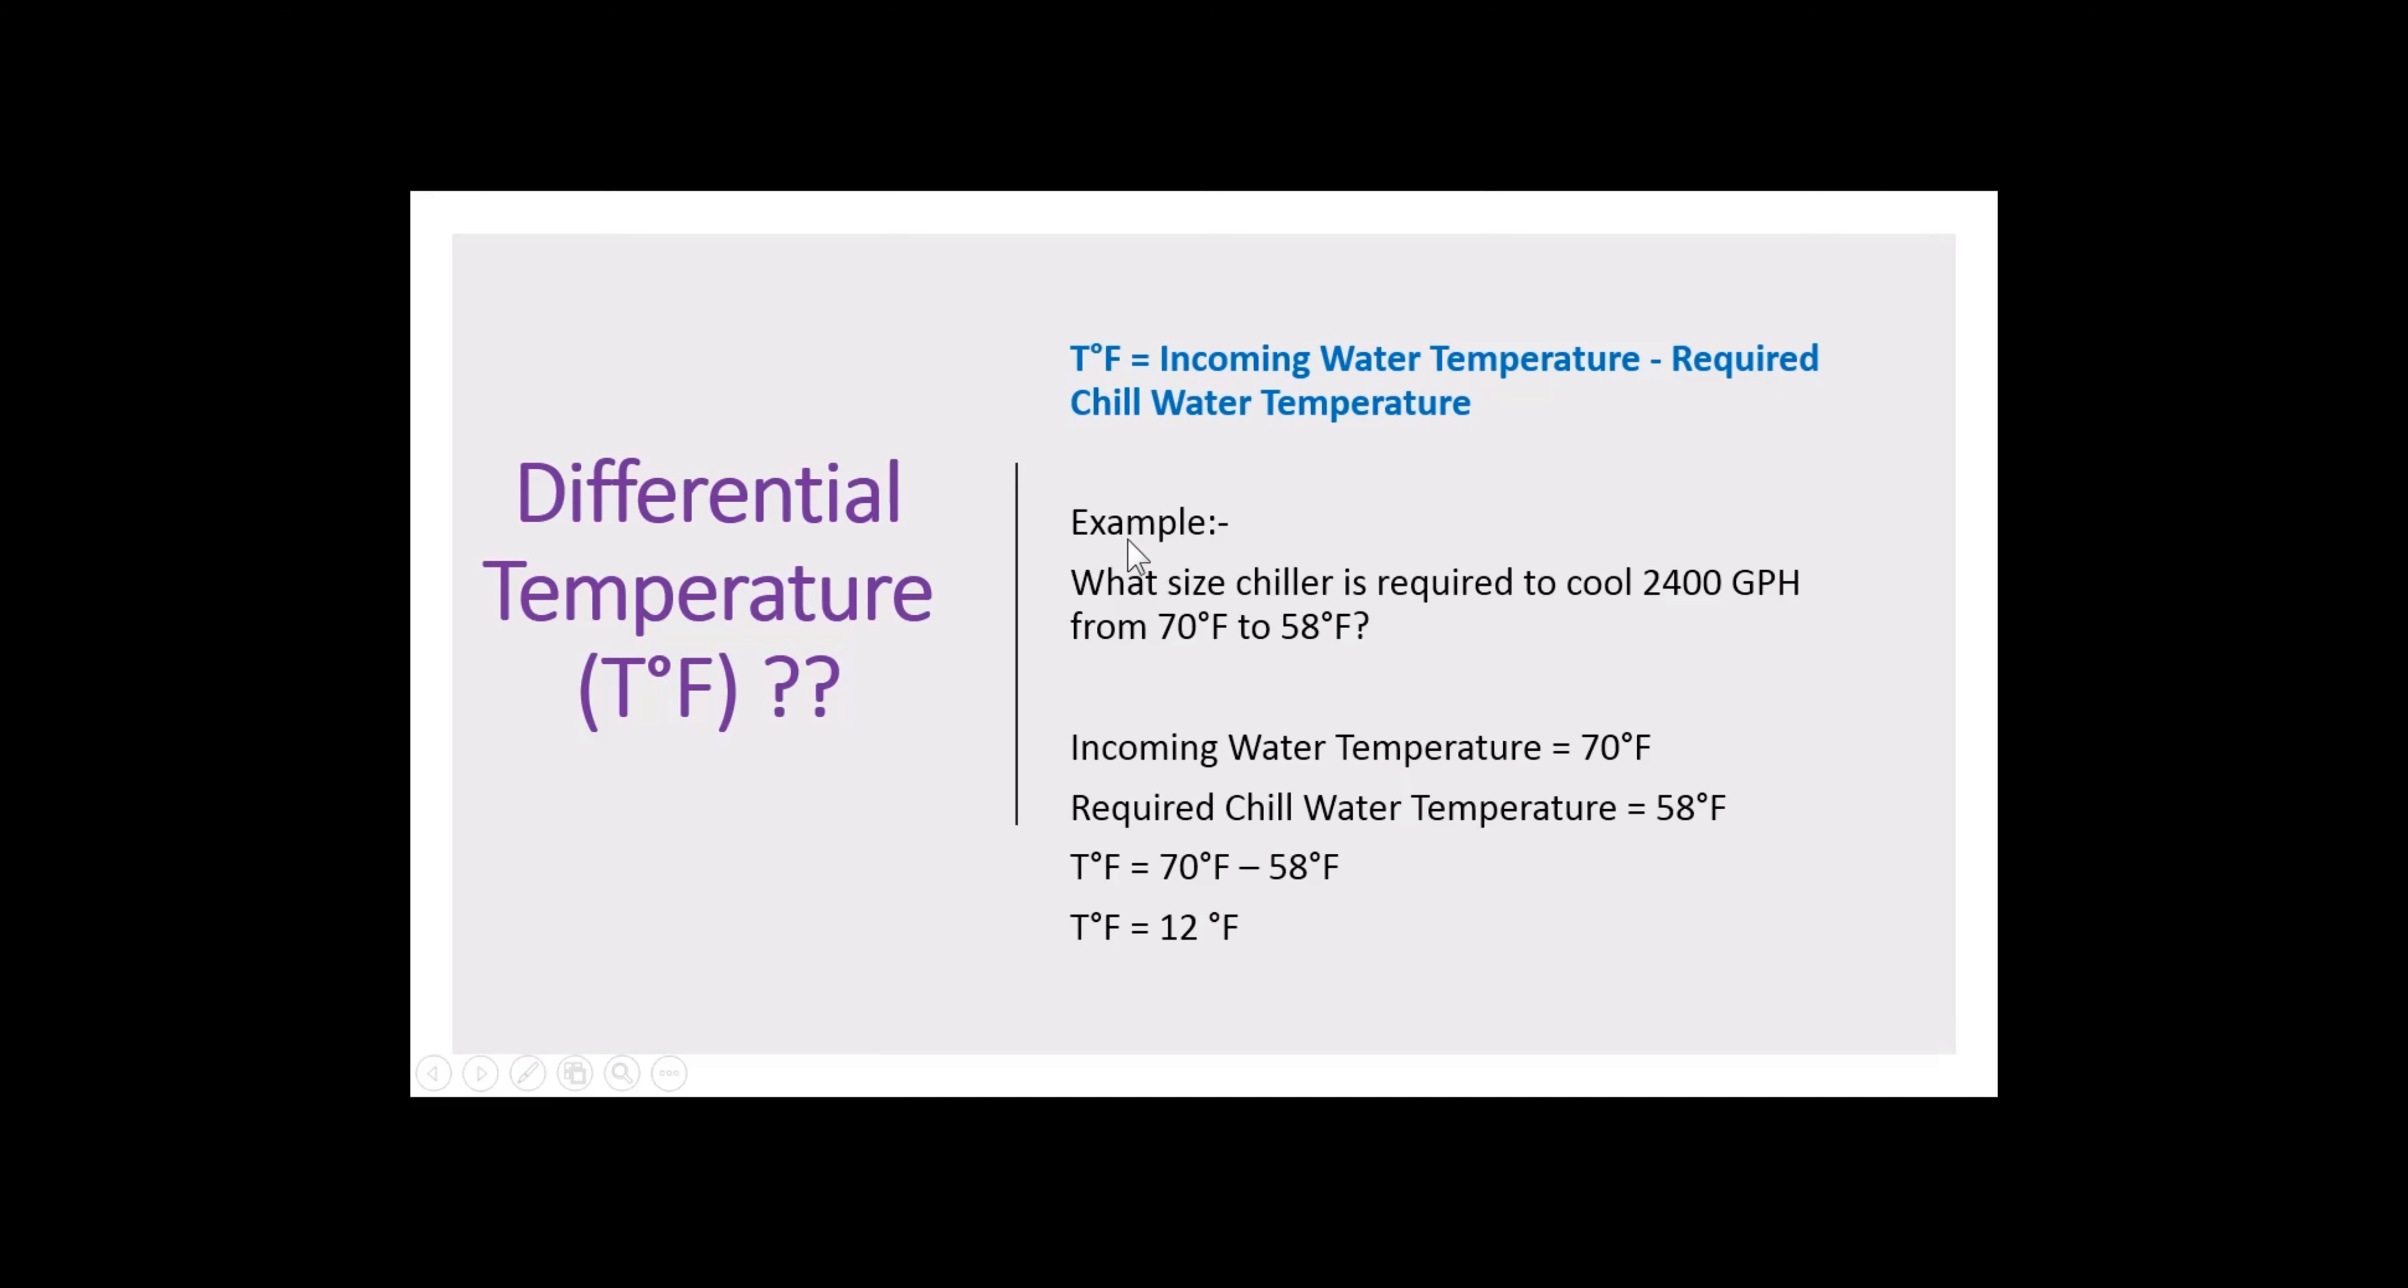Let us have an example. What size of chiller unit is required to cool 2,400 gallons per hour from 70 Fahrenheit to 58 Fahrenheit? Here clearly the flow rate Q is 2,400 gallons per hour. The incoming water temperature is 70 Fahrenheit and the chiller temperature required is 58 degrees Fahrenheit.